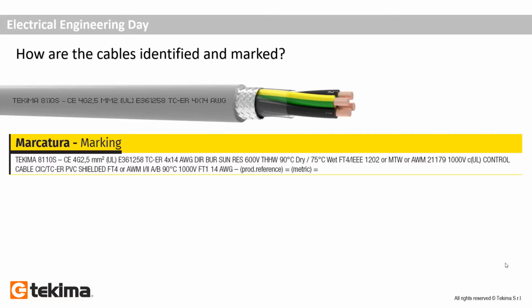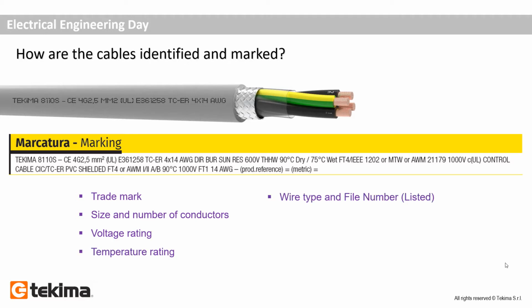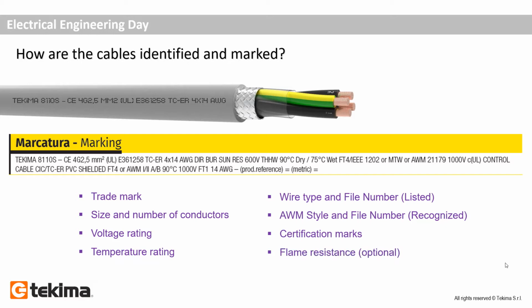Let's see. It's important to say that, contrary to Europe, cable markings in the USA and Canada are strictly regulated. Some indications are mandatory, while others are optional. Any additional requirement must, however, be tested if printed on the cable. This is an example of marking for a Tekima cable. Trademark, size and number of conductors, voltage rating, temperature rating, wire type and file number if it's listed, AWM style and file number if it is recognized, certification mark. All of this is mandatory. The other ones, like flame resistant, are optional. Sun resistant is optional too.